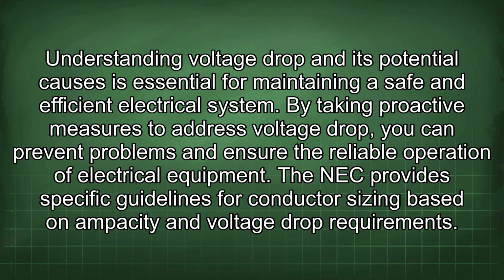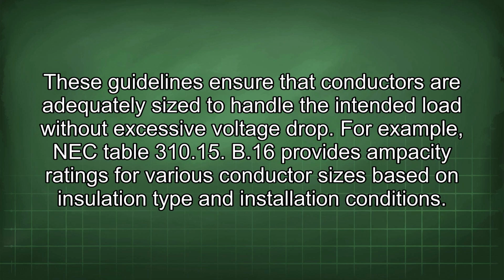The NEC provides specific guidelines for conductor sizing based on ampacity and voltage drop requirements. These guidelines ensure that conductors are adequately sized to handle the intended load without excessive voltage drop. For example, NEC Table 310.15(B)(16) provides ampacity ratings for various conductor sizes based on insulation type and installation conditions.